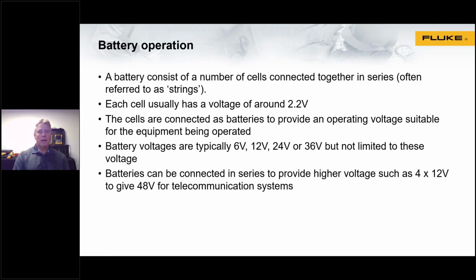Actually, if you have 2.2 volts per cell, that's why typically a battery, if it's good, just for a DC voltage level, is about 12.6 volts. But 24 volt, 36 volt, 48 volts for telecom. So these batteries can be connected then in series to provide higher required voltages.